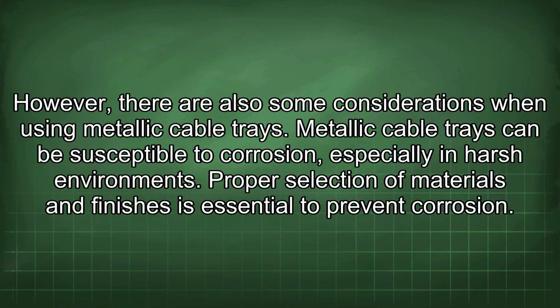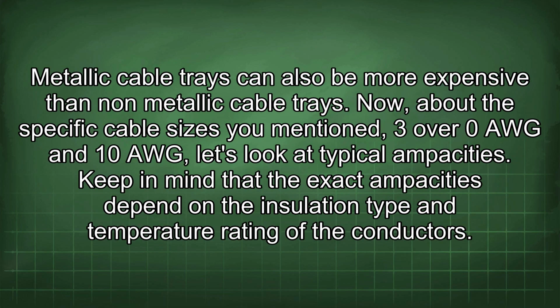However, there are also some considerations when using metallic cable trays. Metallic cable trays can be susceptible to corrosion, especially in harsh environments. Proper selection of materials and finishes is essential to prevent corrosion. Metallic cable trays can also be more expensive than non-metallic cable trays. Now about the specific cable sizes you mentioned, 3/0 AWG and 10 AWG, let's look at typical ampacities.